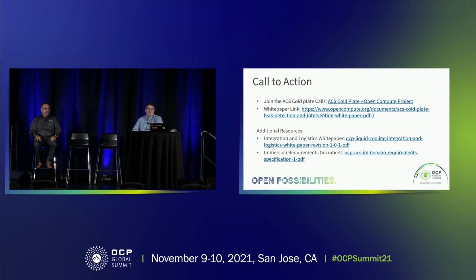So where we're going in terms of form factor, we haven't been pushed to make something smaller, but there definitely is potential. They do make connectors with different bore sizes - that affects your CV, either enabling higher flow rates or a specific pressure drop, and all of that has to be factored in. But a blind mate connector doesn't necessarily have to be as long as the first gen that they did.